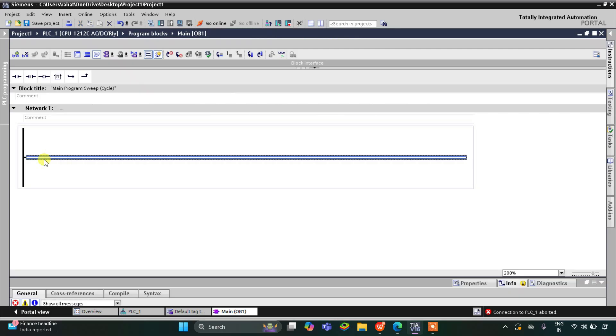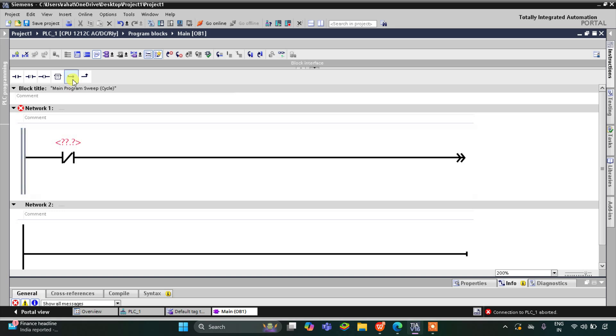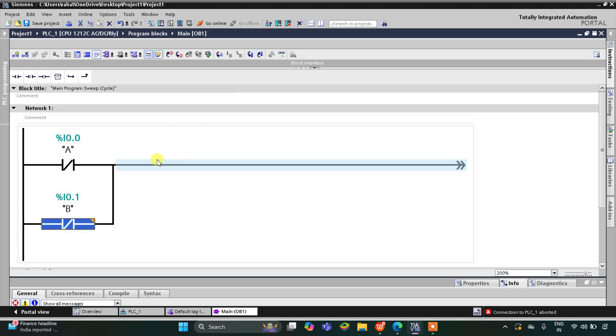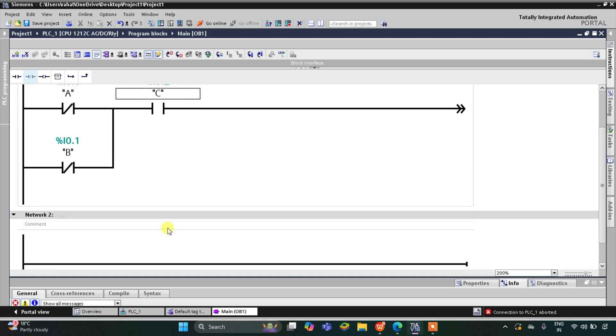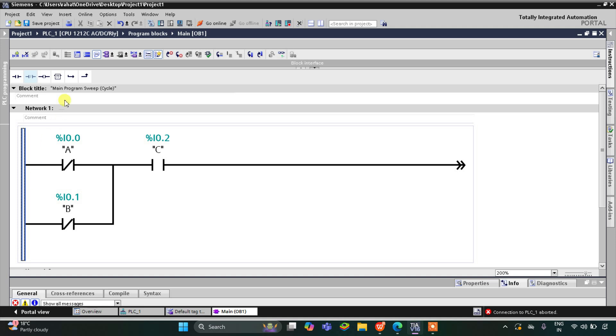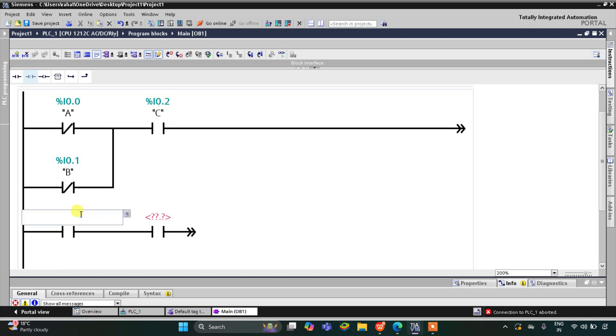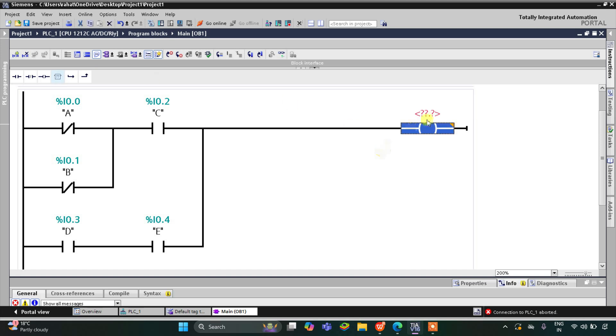In TIA Portal, I'll insert a normally closed contact for A, then open a branch and insert another normally closed contact for B in parallel, then close the branch. Next I'll add a normally open contact for C in series. Then I'll open another branch, connect normally open contacts for D and E in series, and connect it in parallel. Then I'll connect the branch.